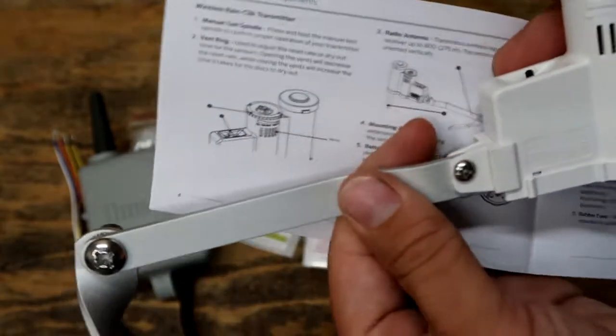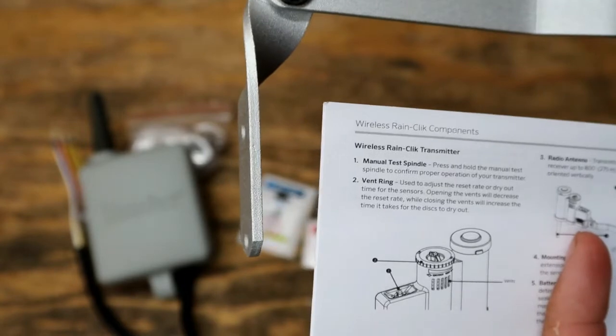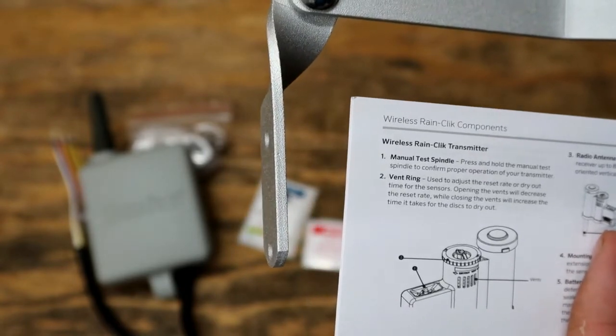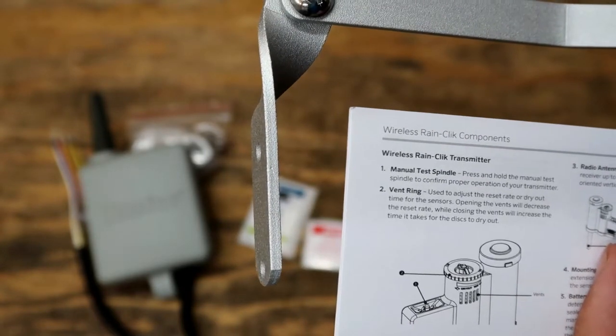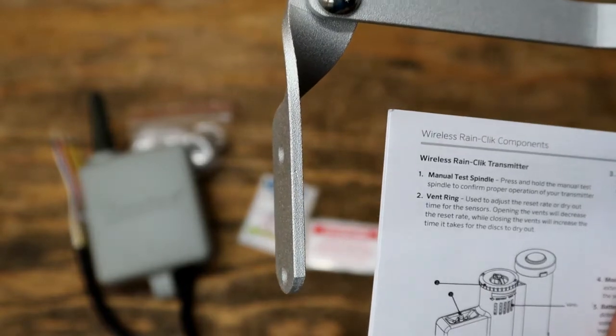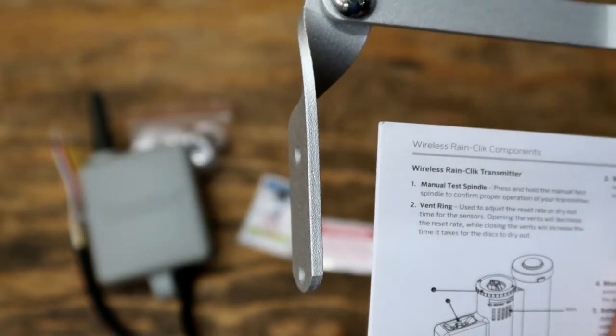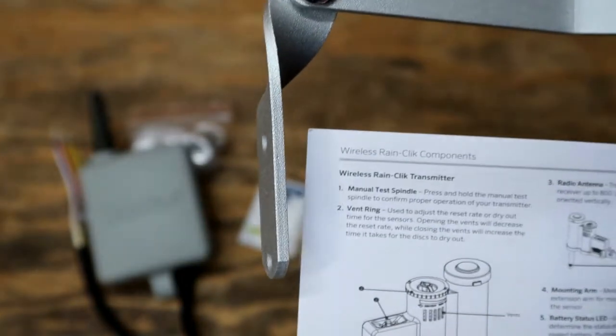Number 2 is your vent ring, like we talked about already. This vent ring is used to adjust the reset rate or dry out time for the sensors. Opening the vents will decrease the reset time, while closing the vents will increase the time it takes for the discs to dry out.